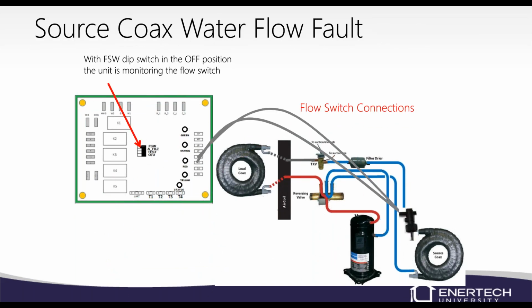If we have a dip switch set for a flow fault and we have a flow switch installed, the paddle switch, and it's coming over here to the terminals, then you could have a refrigerant issue, but it's normally going to be an actual water flow fault. The older units had a paddle switch, and the pressure of the water flowing across it closes that switch. So just depending on how you have the dip switch set up is going to decide if you're monitoring T4 or you're monitoring the actual flow switch terminals.